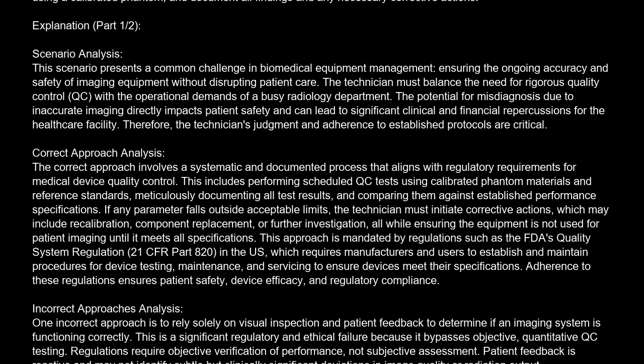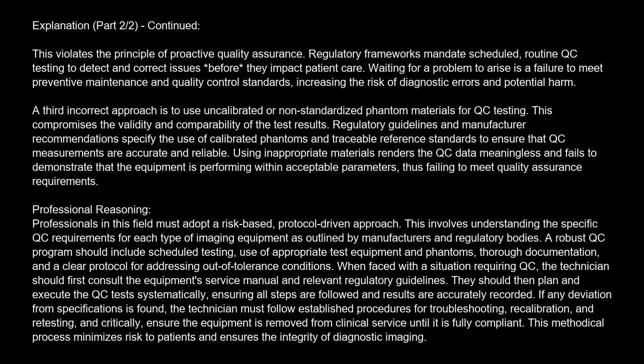Another incorrect approach is to perform QC tests only when a noticeable problem is reported by clinical staff or a patient. This violates the principle of proactive quality assurance. Regulatory frameworks mandate scheduled, routine QC testing to detect and correct issues before they impact patient care. Waiting for a problem to arise is a failure to meet preventive maintenance and quality control standards, increasing the risk of diagnostic errors and potential harm. A third incorrect approach is to use uncalibrated or non-standardized phantom materials for QC testing. This compromises the validity and comparability of the test results.